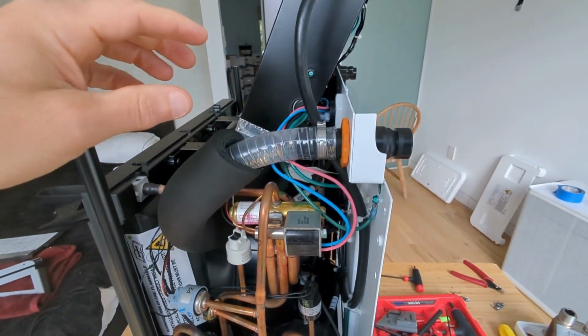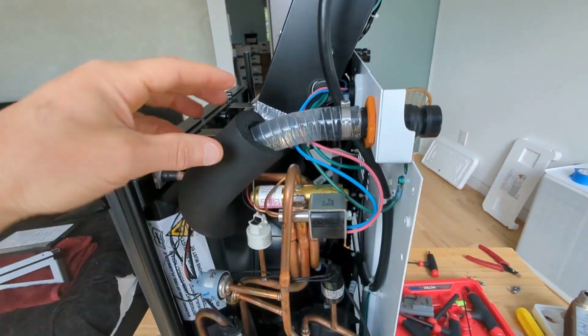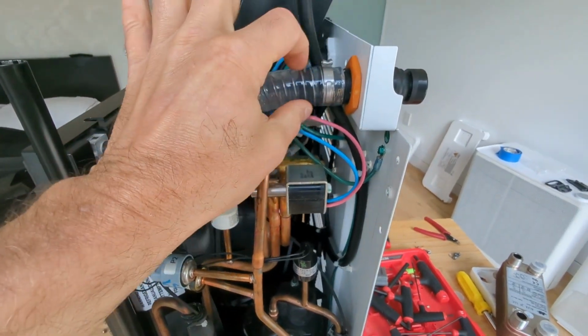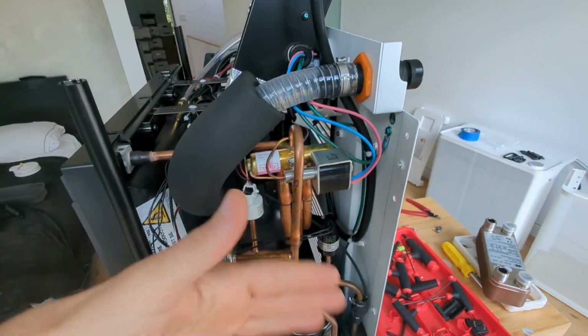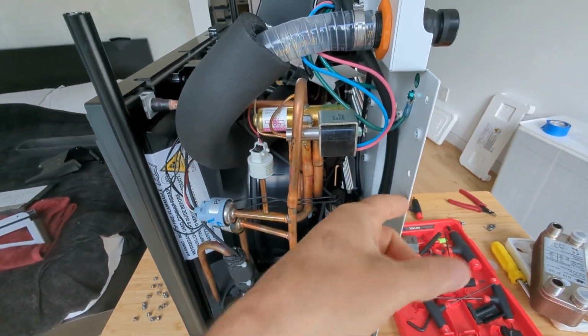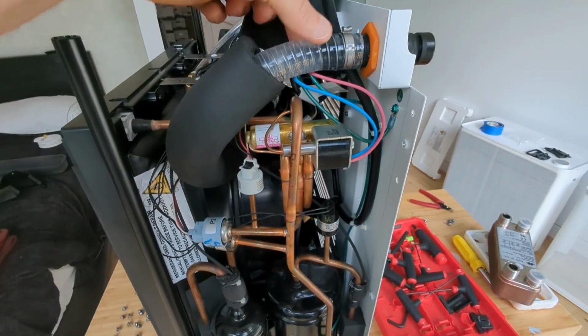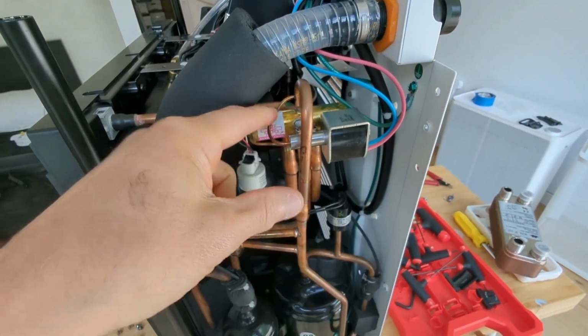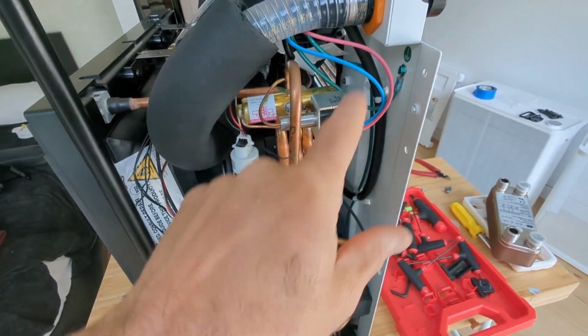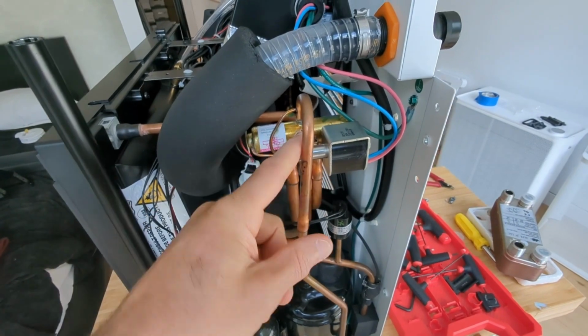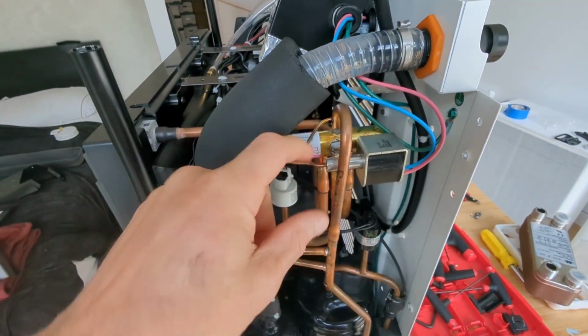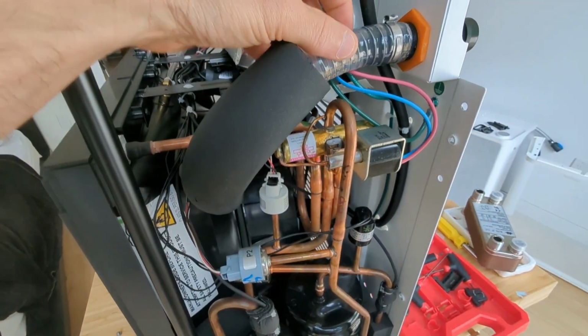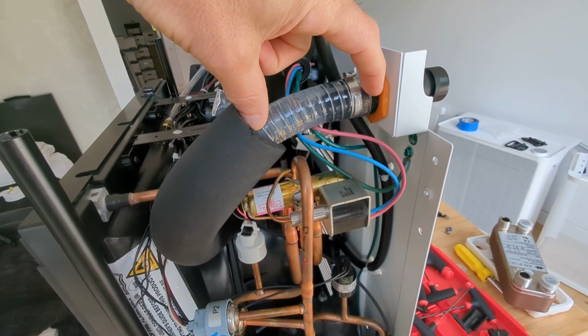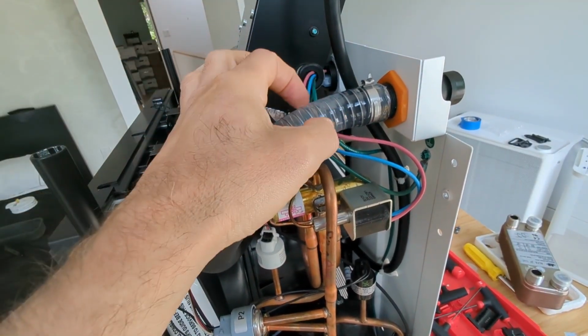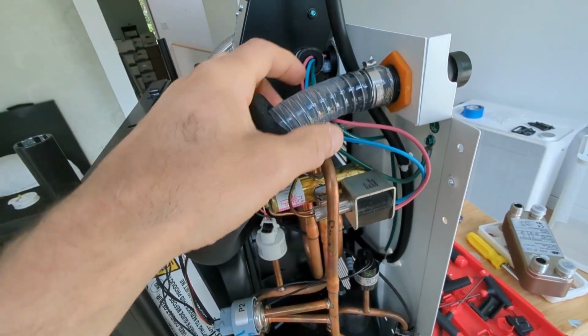It's pretty cool. This is a little bit of a concern on this coolant line - this insulation doesn't go all the way up to the end, so this part is exposed to the constant flow of fresh air going through here because of the condenser fan. In summertime, you're going to have hot, moist air going over this very cold water, and you'll get condensation forming on the bottom of this hose, dripping down all over this stuff - on this reversing valve and on this solenoid. Anytime something's constantly wet like that, there's going to be problems - you'll get slime mold and corrosion. Eventually I think it's going to cause problems. I'd much rather see this insulation go all the way up to here, and you'd get a little bump in efficiency because you're not heating up this water.